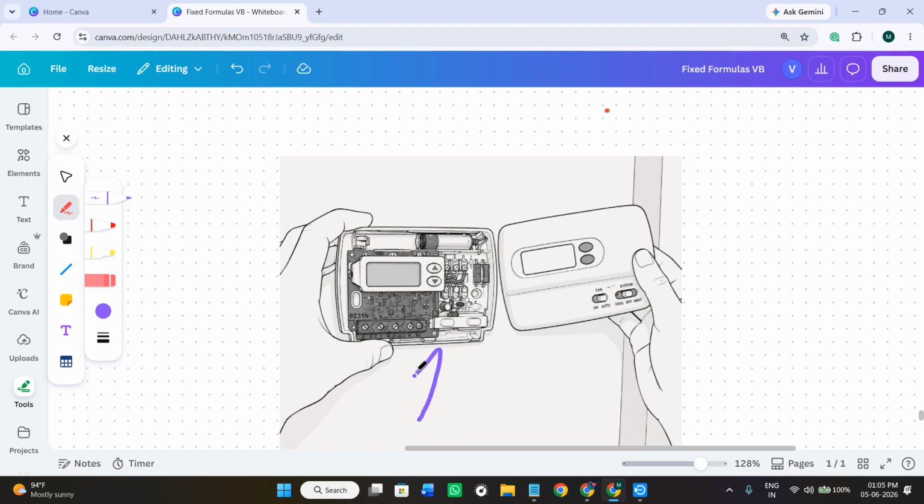Now you can also simply perform a reset. You just have to remove the thermostat batteries if applicable. Then you just have to restart the thermostat through its menu. Then you need to switch the boiler off at the fused spur and power switch for at least 30 seconds before turning it back on. Often a communication fault clears after both devices reboot and reconnect.